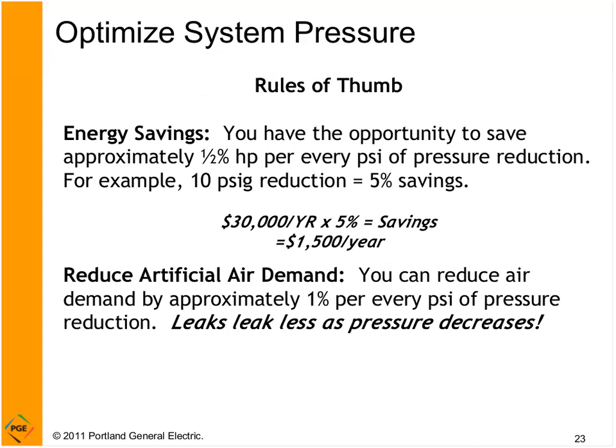Here's a useful rule of thumb: on average, your system will save about half a percent in horsepower for every PSI reduction. Just like climbing a mountain — don't climb to the top of Mount Hood to walk back down; just go to Meadows. The math: on a $30,000 per year 100 HP compressor, dropping 10 PSI saves about $1,500. It might take 10 minutes to adjust pressure set points — a very high-value action.